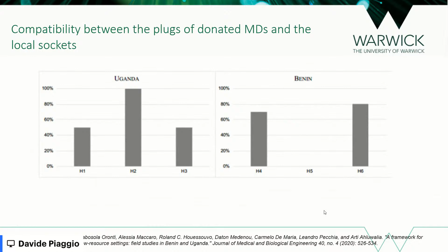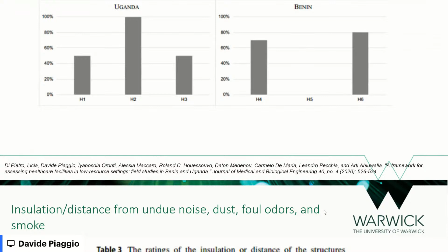One issue that we also highlighted is the incompatibility between the plugs of the donated medical devices and the local sockets. You can see that in one case, in this hospital in Benin, we had 0% compatibility. This means that the healthcare workers who need to use these devices will resort to using adapters, which is not a very good solution because it can hinder the safety of the device. And I think we can see in a few slides what this means.